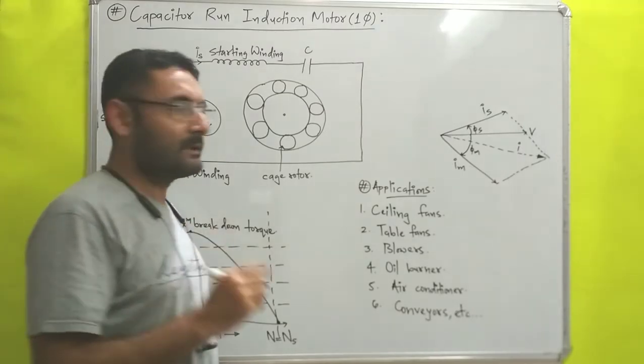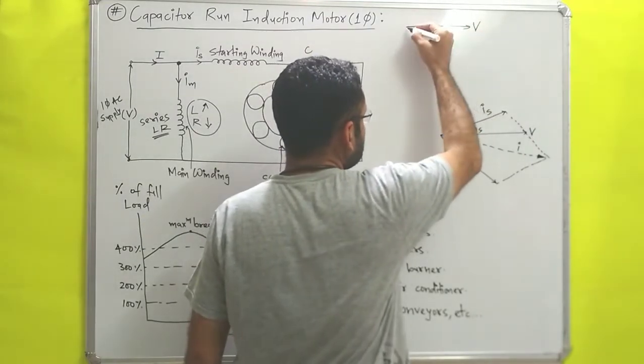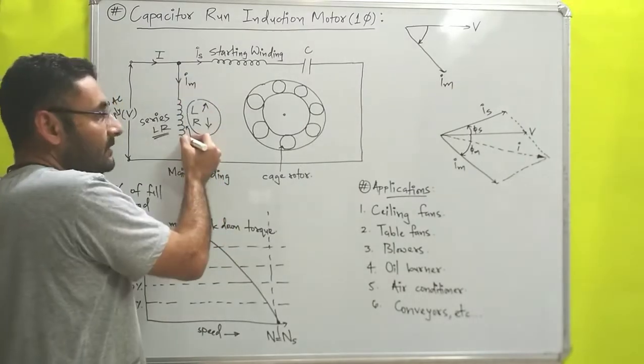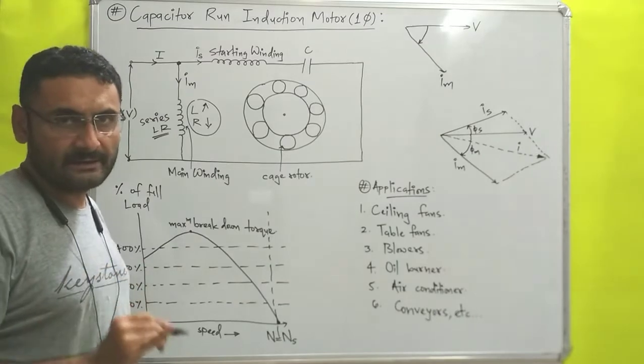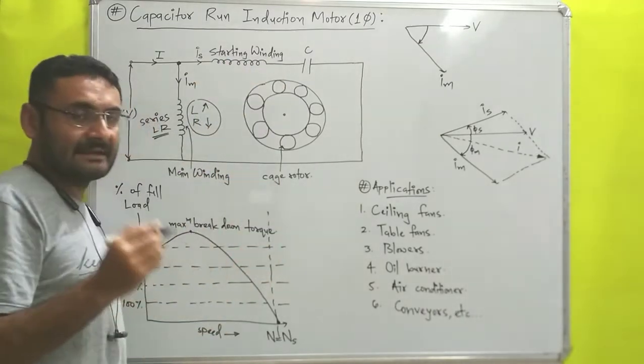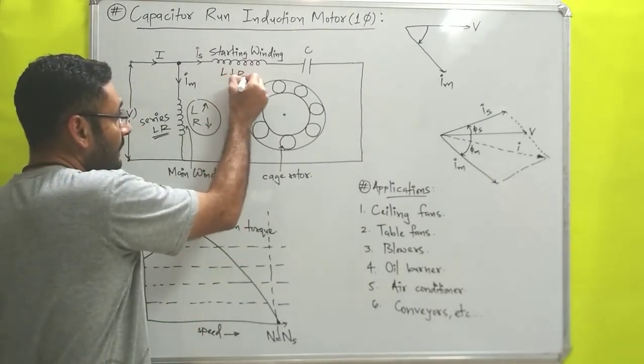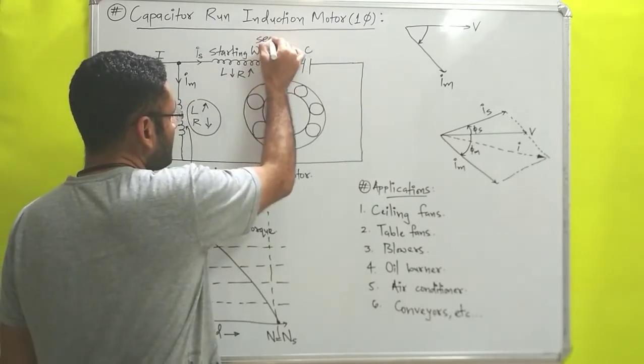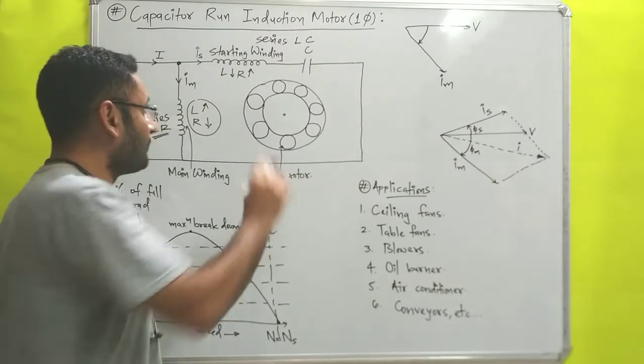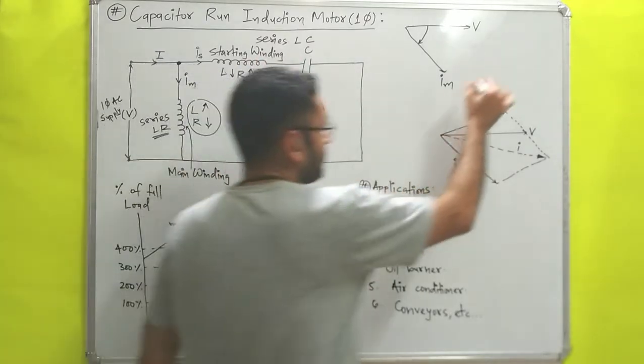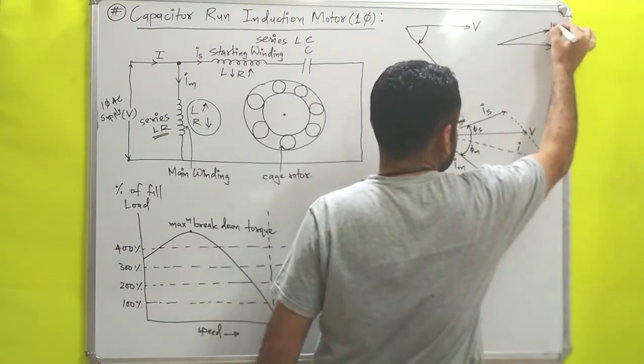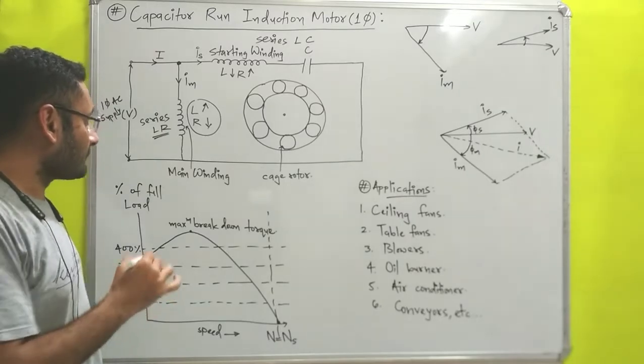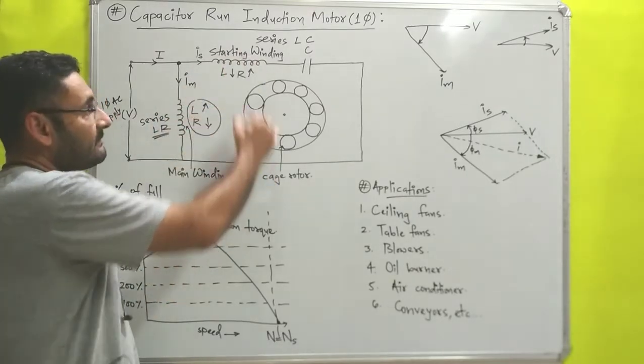For a series LR circuit, the current Im lags behind the voltage. Similarly, the starting winding is designed to have low inductance but high resistance, and it is connected in series with a capacitor, making that branch a series LC circuit. For a series LC circuit, the current Is leads the voltage by some phase angle. Importantly, that capacitor is not connected with a centrifugal switch — that is the key difference in this motor's construction.